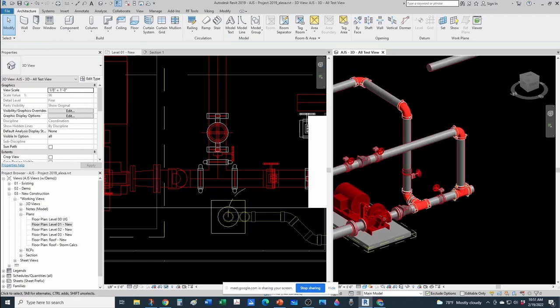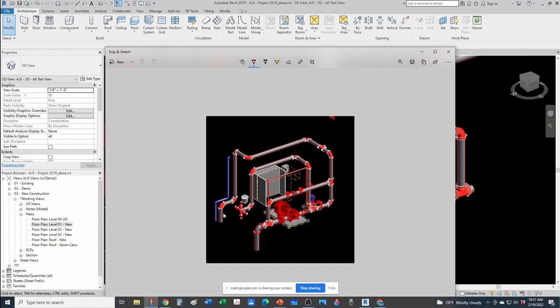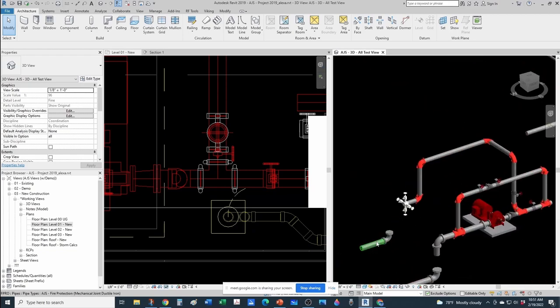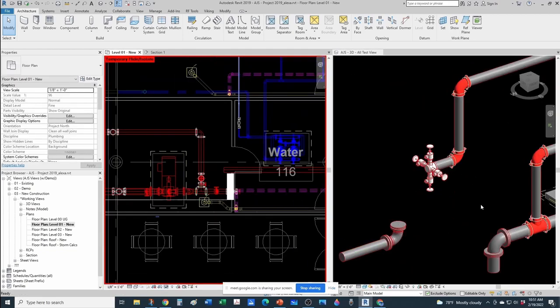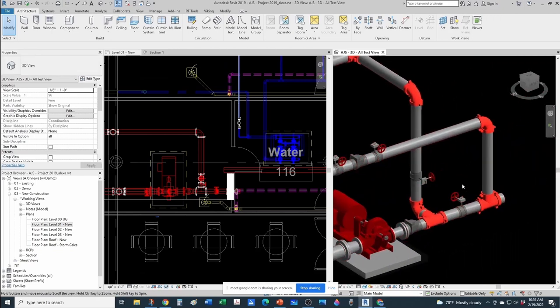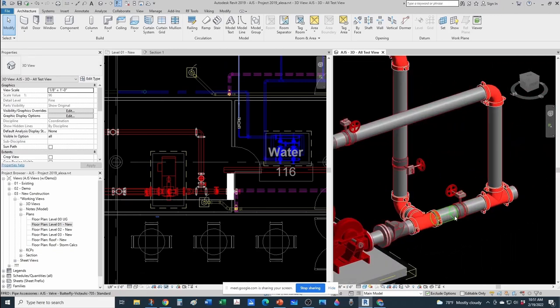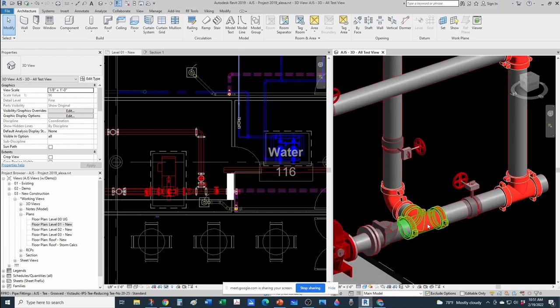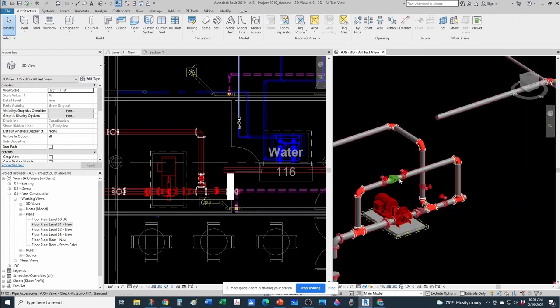later, right? Now that we are at our discharge, the only thing we need to join is that line that is coming from the fire department connection, right? Which is already at high pressure. That's why you don't want to connect it at the suction. So let's go with that line. And sometimes you'll see this valve happening on the vertical, and this wouldn't be coming out horizontally either. This would be coming out vertically, but I'm going with the textbook example just to be more clear.